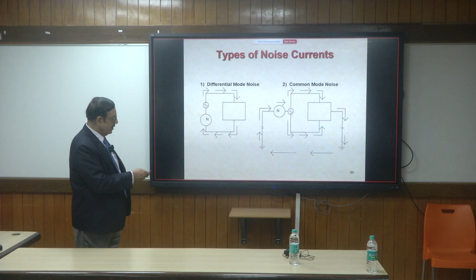It returns to that. Now the question may be, I have equipment on the table and it is very well insulated from the floor, then how does the current flow through the mother earth? The question is, it's not resistive, it's capacitive coupling there once again. So you may have a small capacitive coupling there, and the current flows. This is a high frequency current that flows through the capacitance, and that's how things return back to neutral. And more particularly, because the supply side AC supply, one terminal, the neutral, is always earthed at the substation. So that completes the path back to the supply substation.